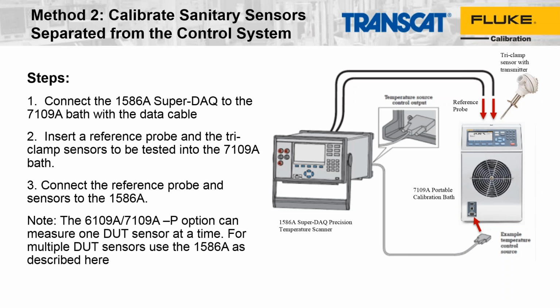All right, so the second method, this one's a little more complicated, and we're bringing in another piece of equipment in case there are more sensors that need to be calibrated. The 7109A, if you have the P-board option, the process electronics option, will accommodate measuring one DUT sensor, but if you have multiple DUT sensors, because the tank holds 4, then you will have to bring in a readout that will measure those 4 sensors. And so the readout we're using in this example is the Super-DAQ 1586A, and it has an advantage of being able to connect to the 7109A, and now you can run a program from the Super-DAQ that will take data on the sensors and record the data, and we'll go through those steps.